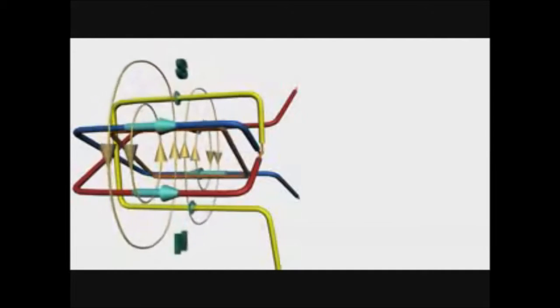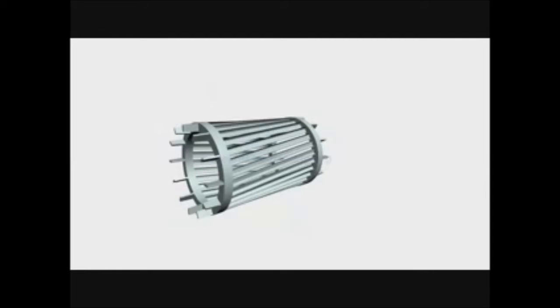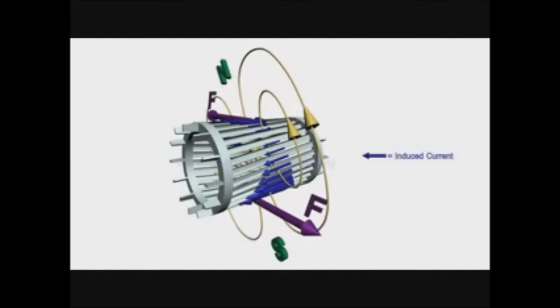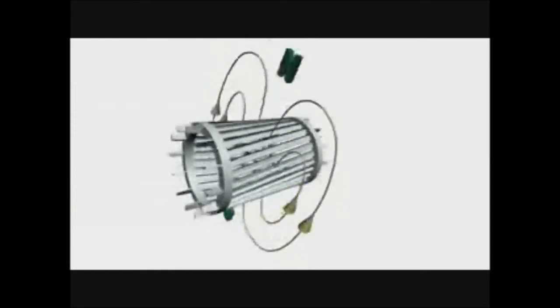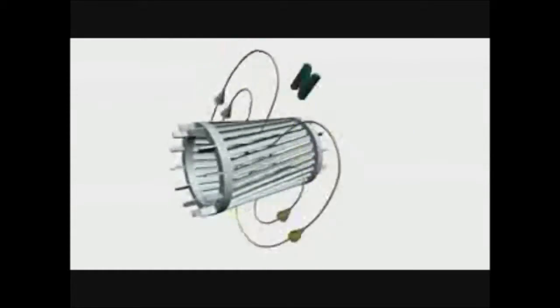A similar phenomenon happens inside an induction motor also. Here, instead of a simple loop, something very similar to a squirrel cage is used. Three-phase AC current passing through stator winding produces a rotating magnetic field. So, as in the previous case, current will be induced in bars of squirrel cage, which is shorted by end rings, and will start rotating. That's why it's called an induction motor. Electricity is inducted in the rotor by magnetic induction rather than direct electric connection.